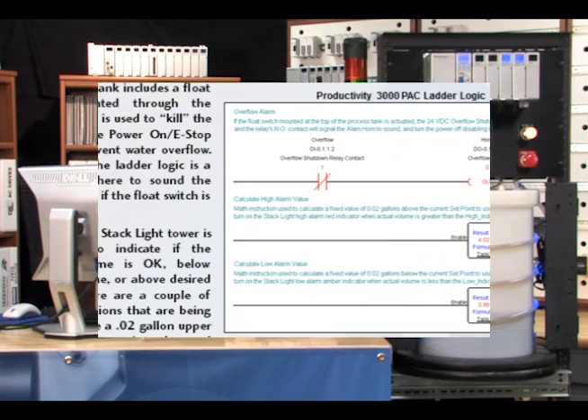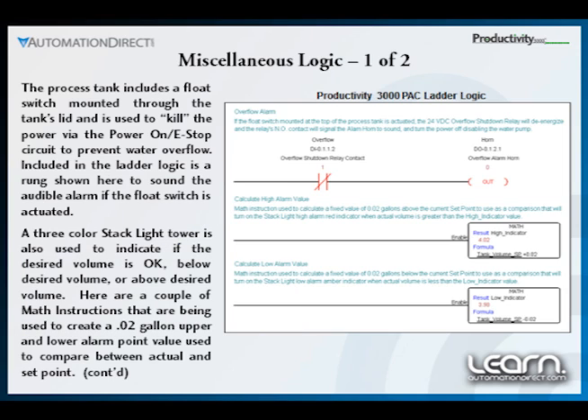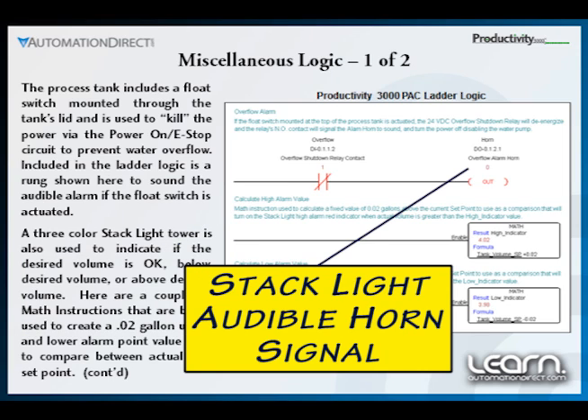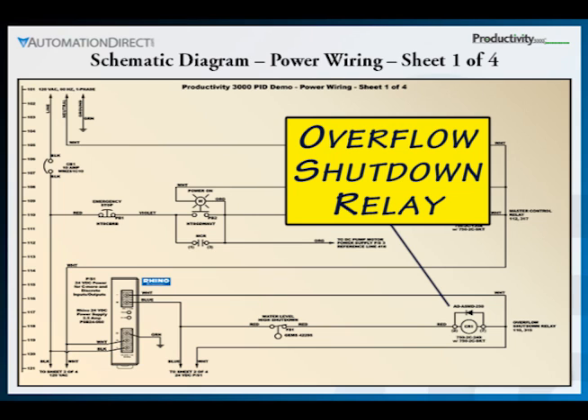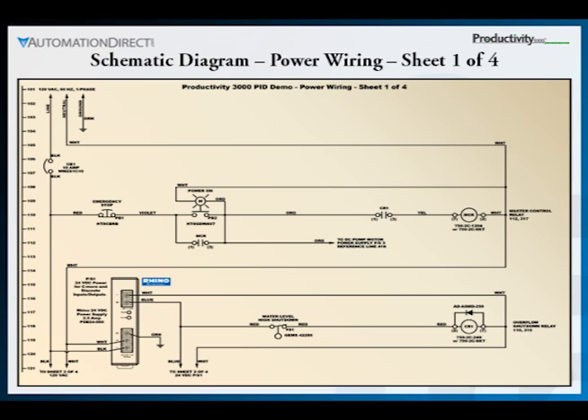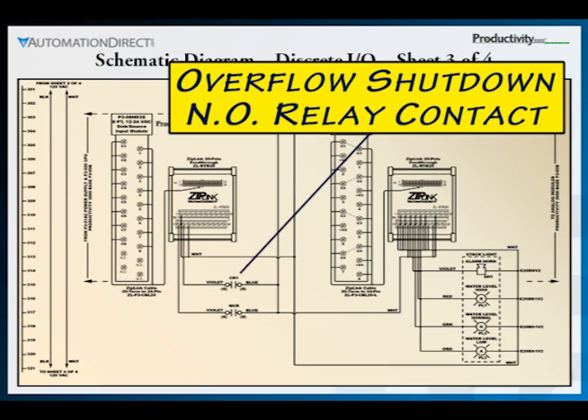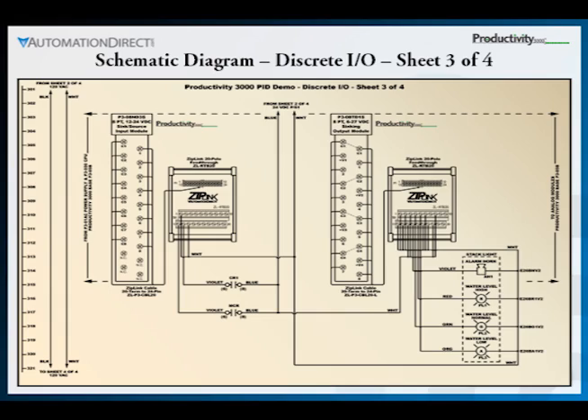We can program our signal from the high level alarm float switch relay to give us both an indication on the C-more touch panel that there is a problem and also sound the audible alarm horn on our stack light. Referring back to our schematic diagrams, the float switch is wired so the overflow shutdown relay is normally energized if conditions are OK, and a normally open contact is wired into the master control power circuit to allow it to be energized. Another normally open contact from the overflow shutdown relay is wired to input 2 on our P3-08ND3S DC input module, which allows us to monitor the status of the overflow shutdown circuit.